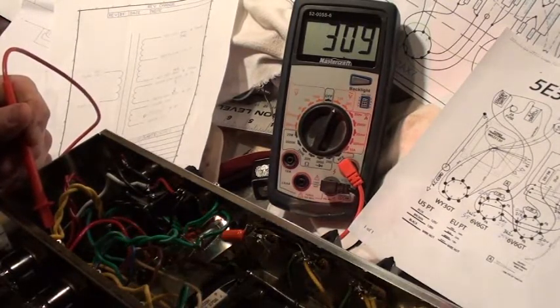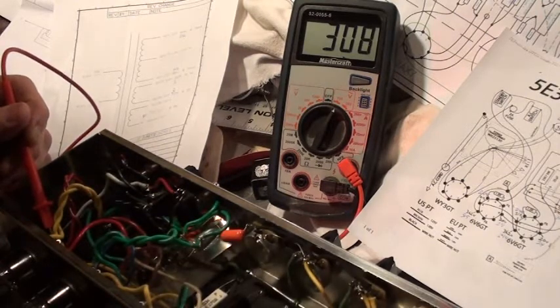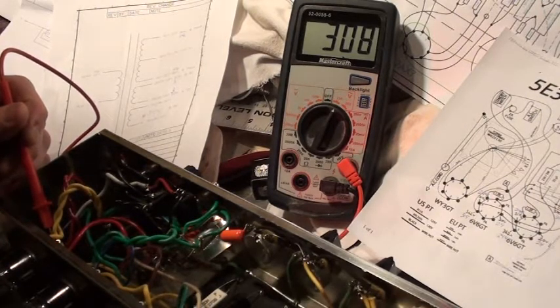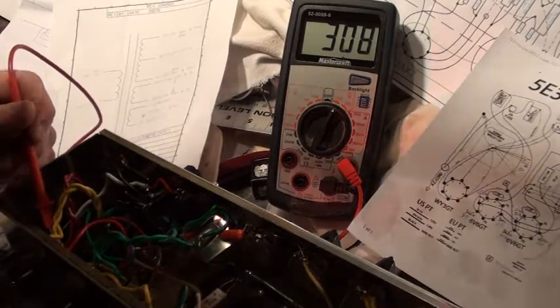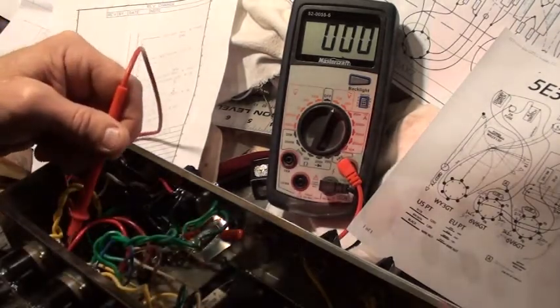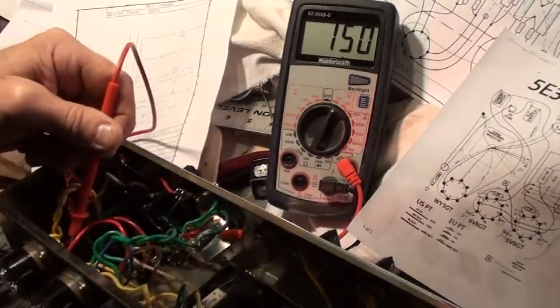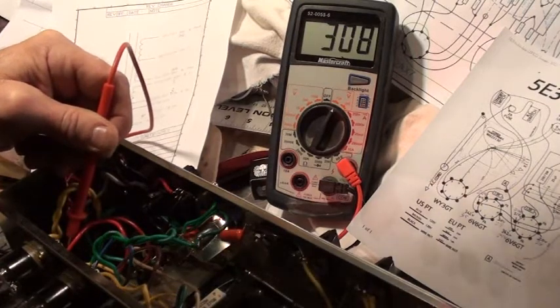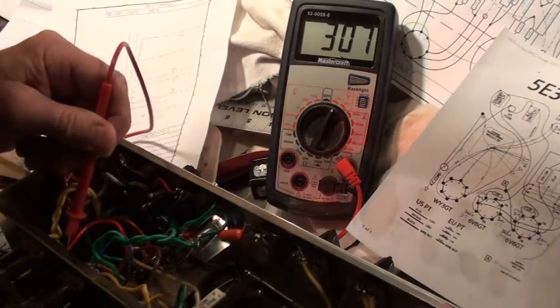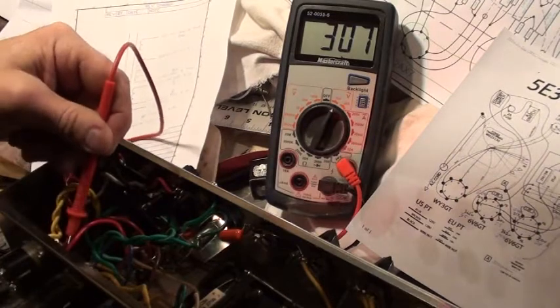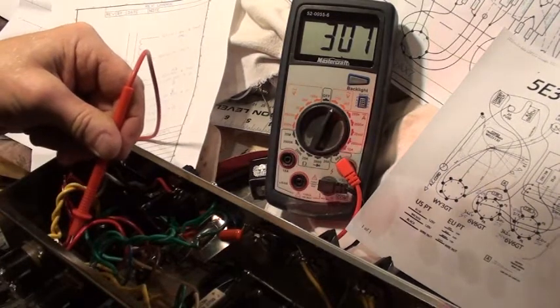I have 309. My schematic for the transformer reads that it should be 384. And my other terminal, which is number 8, which is reading 307, or sorry, number 6. My 4 and 6 are my high voltage connections.